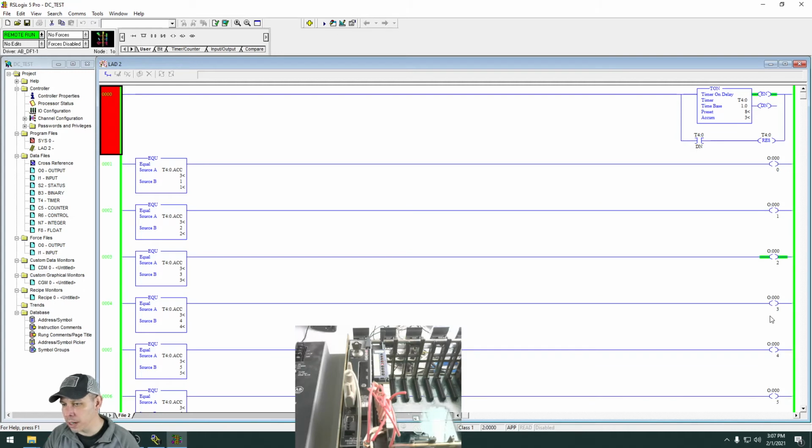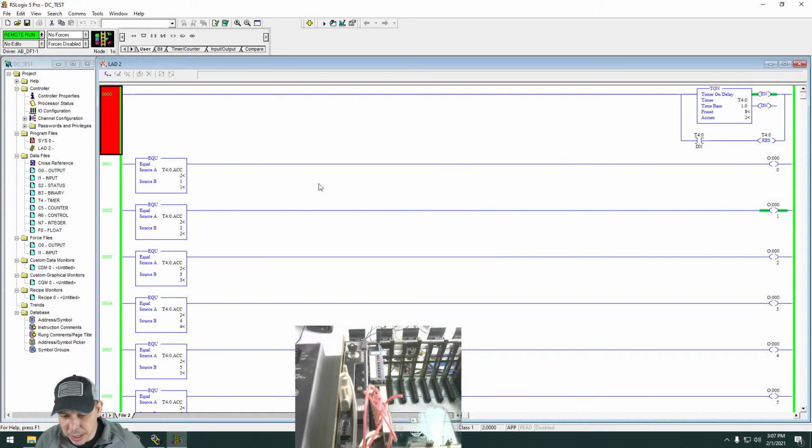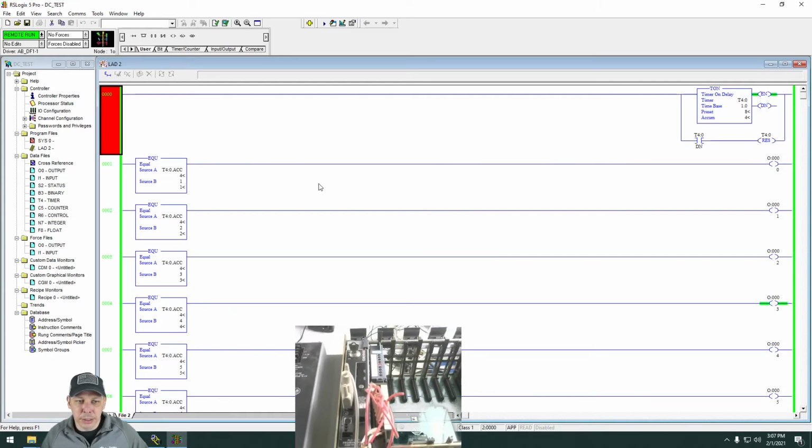So you see the green here, meaning it's energized as it goes through. Or if you have contacts go into it, normally open or normally closed, or XIC or XIO, as Allen Bradley likes to call them. Moving the camera around, it's still good there. It'll just highlight that little section. It won't highlight the entire rung. So that's what this means here.